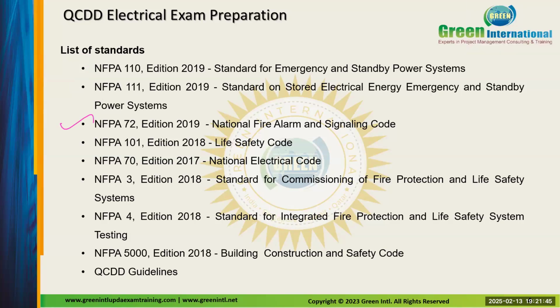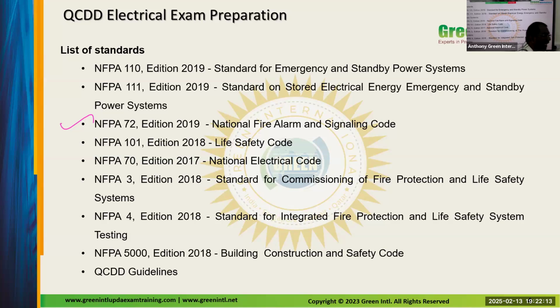Then we have a few devices: smoke detector, heat detector, all called initiating devices. Then we come to other devices, called notification devices. And the last items are interfacing devices, interfacing with the CCTV, interfacing with the HVAC panel. So for fire alarm systems we have 4 broad categories: control panel, initiation devices, notification devices, and interfacing devices. All of these we refer to from NFPA 72.